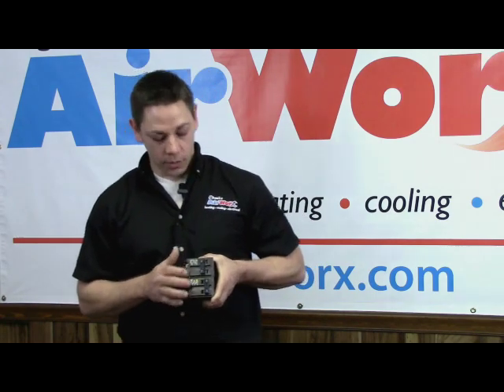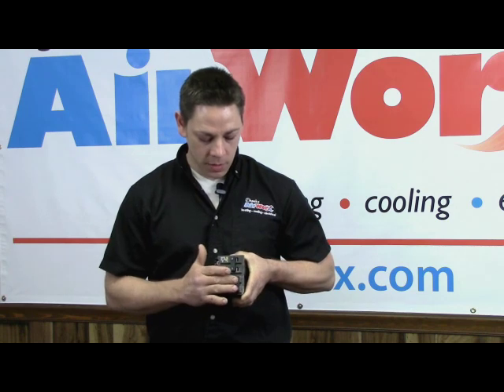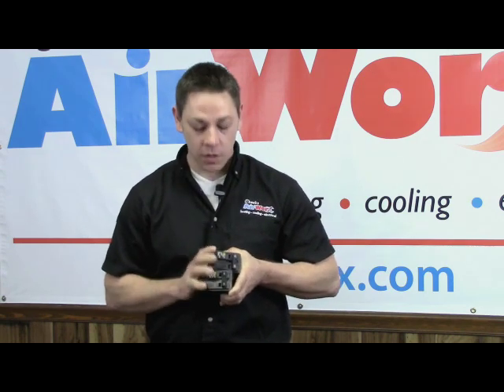Typically what you're looking for in your panel is for one of your breakers to be slightly off from the rest of your breakers. These breakers are in the on position, but this breaker is not. What you want to do is turn the breaker all the way to the off position and then flip it forward to the on position.